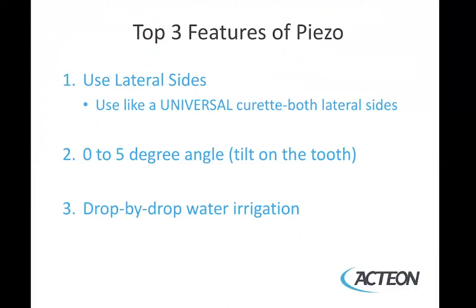The second unique feature is that you will use the piezo with a zero to five degree angle or tilt on the tooth. If you learned magnetostrictive first, you typically use that at a 15 degree angle, so when using the piezo you'll want to close your angle a little bit, using a zero to five degree tilt on the tooth.